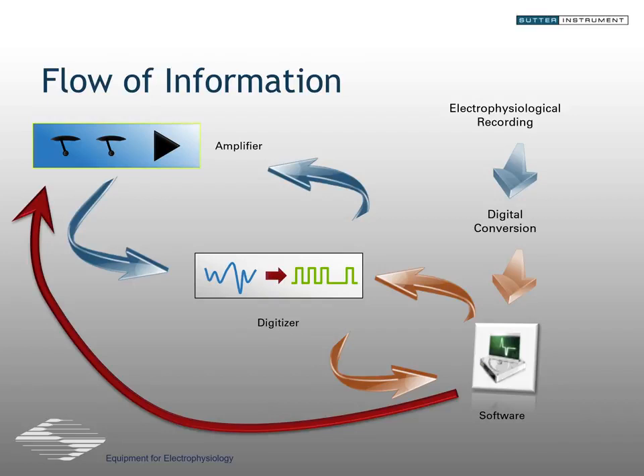Now here, with these multiple components all connected via cables and connections, we set ourselves up for potentially a little bit of trouble. Not only is it more time consuming to install with all this cabling and connections, you risk the possibility of wiring things incorrectly and having to troubleshoot proper connections. But as many of you who perform electrophysiology experiments know, oftentimes there's a certain amount of troubleshooting and tracking down the source of things like noise. You're generally tracing those sources through the cabling and through the connections of your system. What we've done at Sutter, by integrating the digitizer into the amplifiers, is dramatically simplify this whole flow of information.